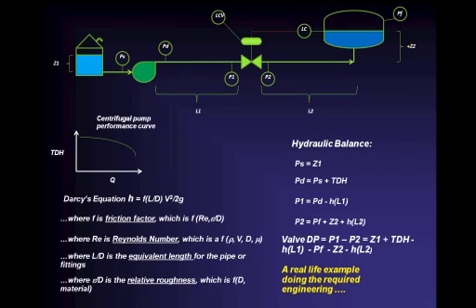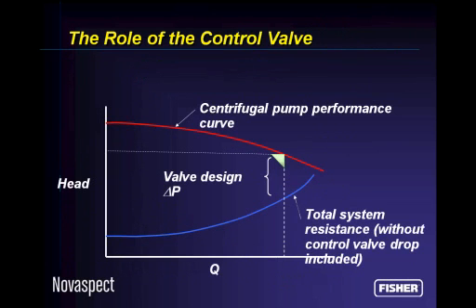What we demonstrated to him was that we could essentially take the control valve out of the pipe and just put a short piece of 12-inch long piece of pipe in there, and he would only get 7% more flow with no valve. So he wanted 25%. We demonstrated by doing this hydraulic balance that there was no way he could achieve his objective.